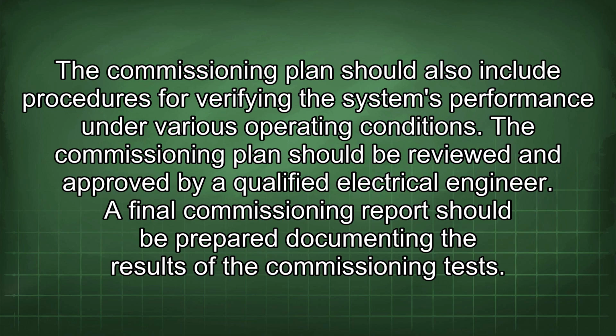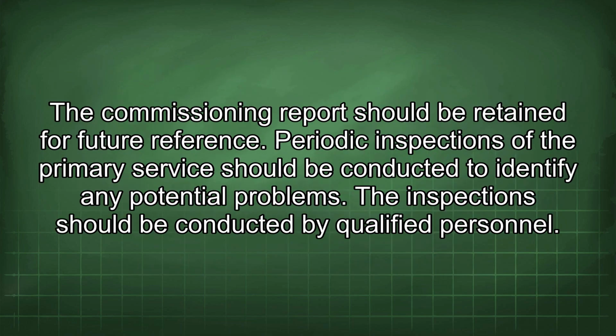The commissioning plan should be reviewed and approved by a qualified electrical engineer. A final commissioning report should be prepared documenting the results of the commissioning tests. The commissioning report should be retained for future reference. Periodic inspections of the primary service should be conducted to identify any potential problems. The inspection should be conducted by qualified personnel.